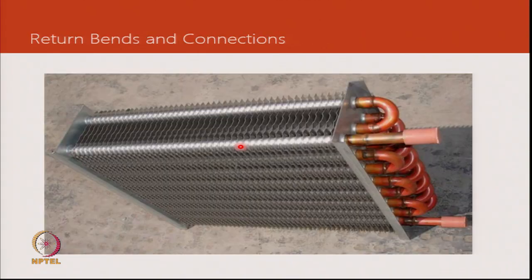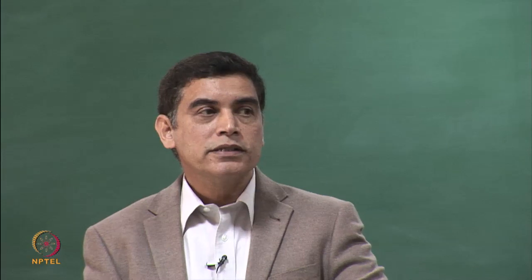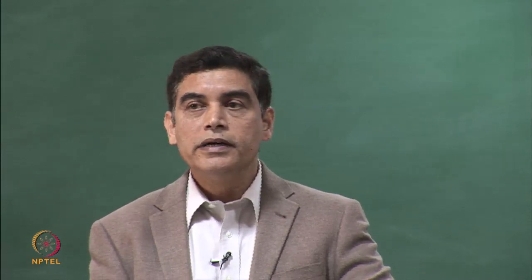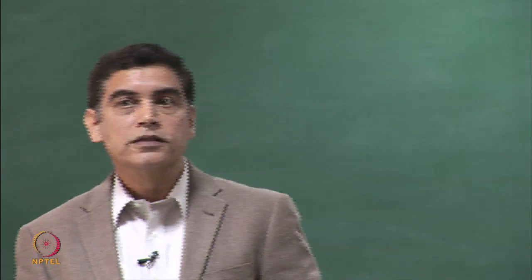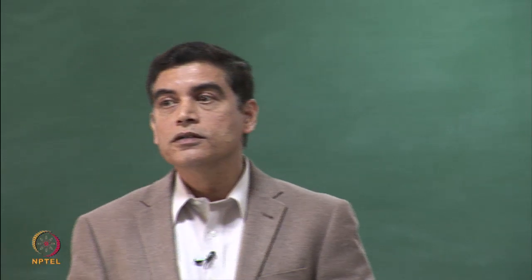After the tube expansion is done, the return bends are brazed. Once the brazing process is completed, the coil is subjected to leak testing, and on a random basis at a certain frequency, burst tests are done to ensure the coil integrity is intact and no leaks or unfamiliar situations will occur during operation.